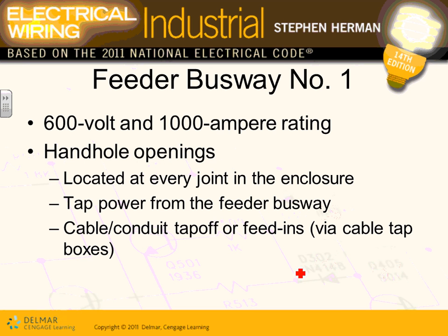In our project, gentlemen, we have two feeders. Feeder number one here is right here. I don't know if you guys can see it. If you have your blueprint, you should see that blue here. It's called feeder number one. Feeder number one in our project, believe it or not, has these voltages: 600 volt max at 1,000 amp. We're pulling 480 volt from it.